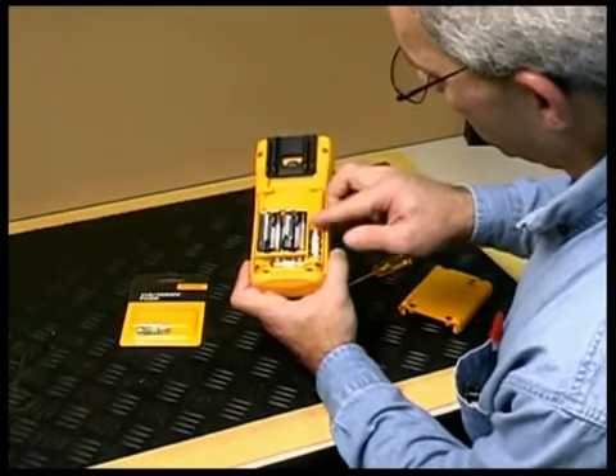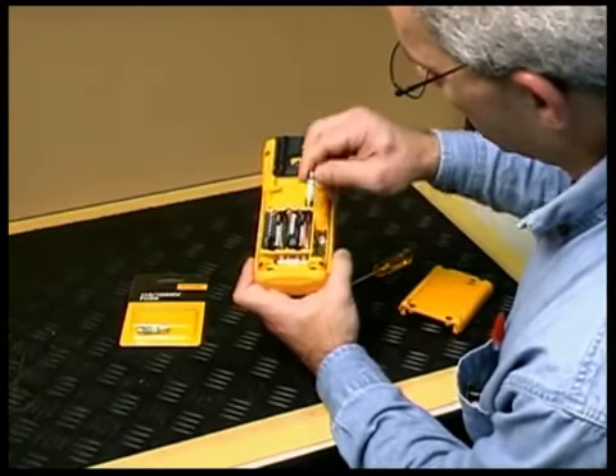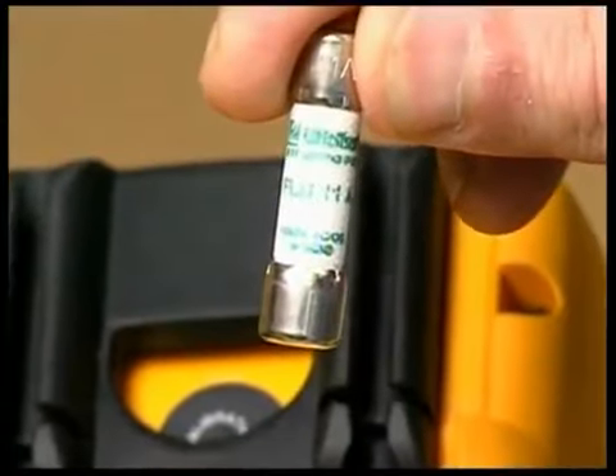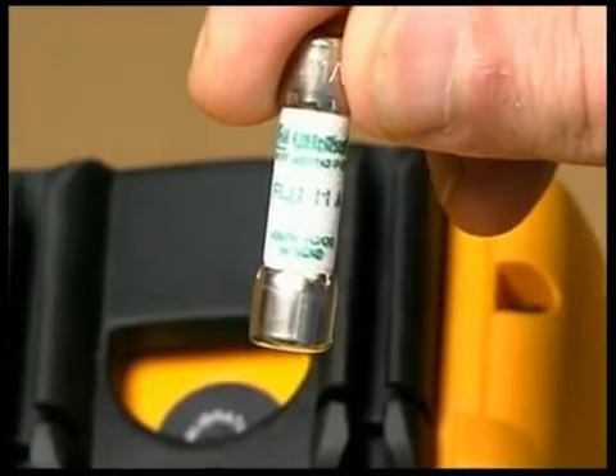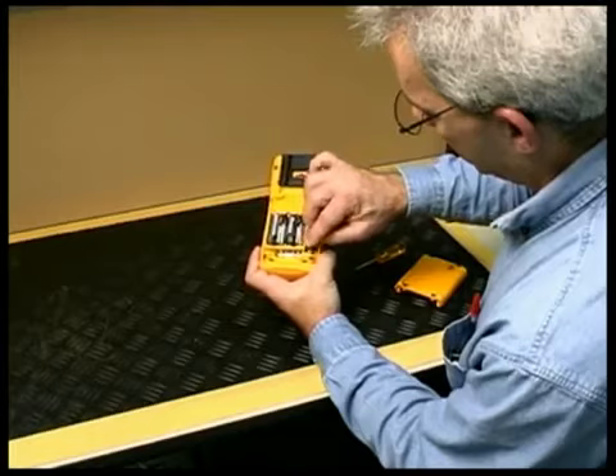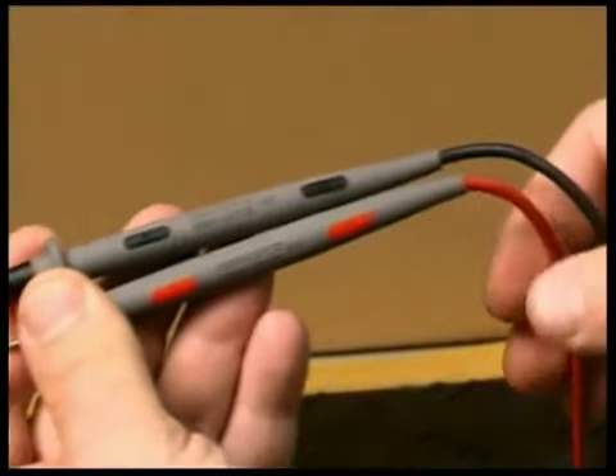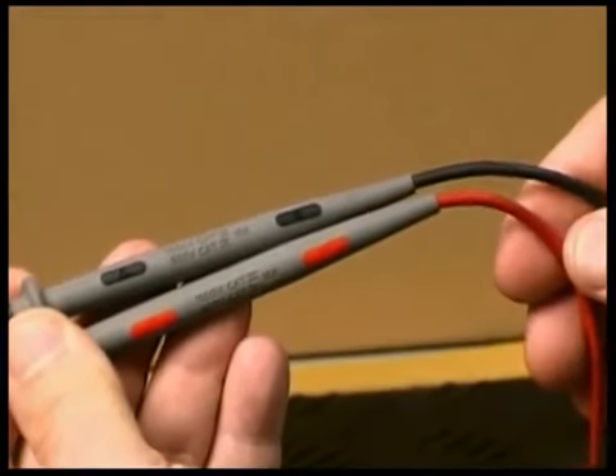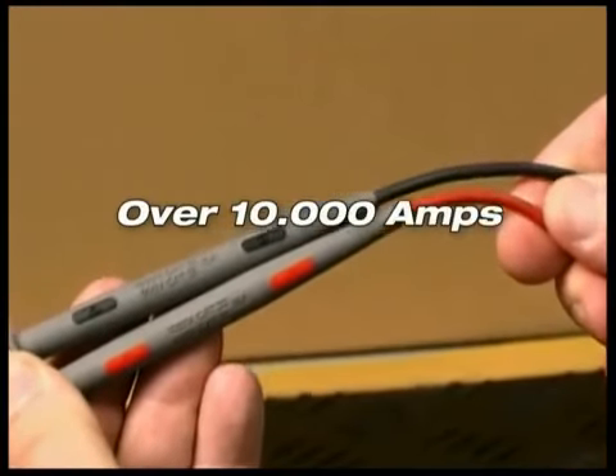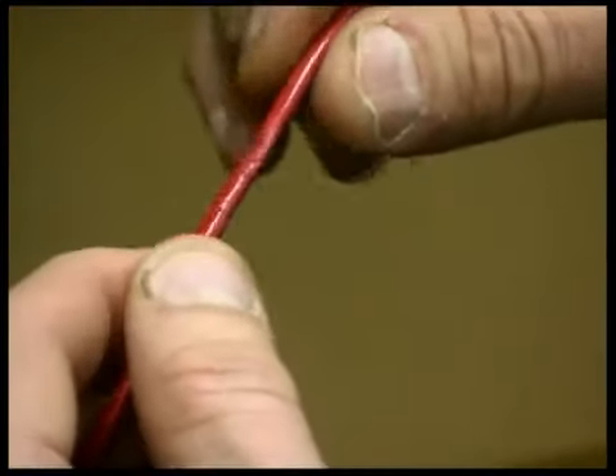Never use the wrong fuse. Only use high-energy fuses specified by the manufacturer. The Fluke meter system, which includes the meter's internal circuitry and fuses, and the test probes, work together to properly interrupt fault currents that exceed 10,000 amps. Accessories can also contribute to danger.